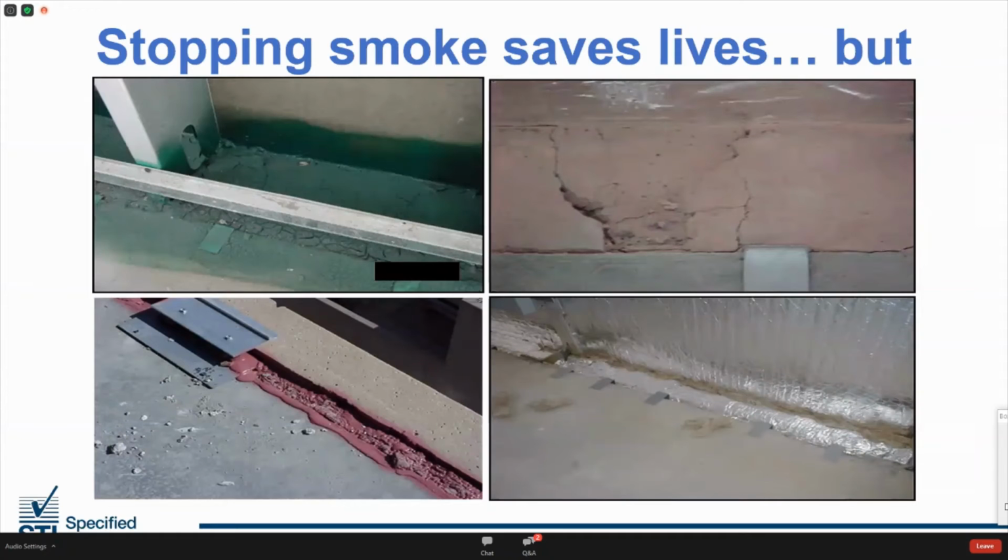But we continue to see damaged or incorrect installations quite often. This could be due to spray damage because of exposure to water before it is cured, hard brittle compounds that crack once cured, incorrect caulking that has washed out due to water exposure, and untested solutions like simply stuffing pieces of mineral wool insulation into the void.